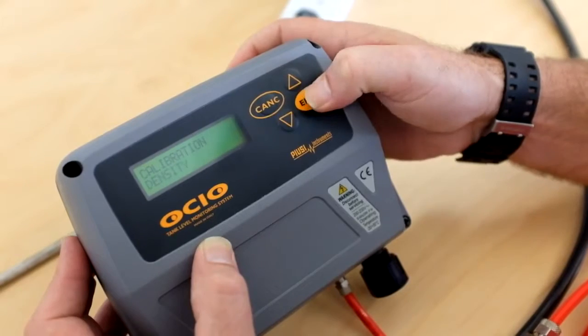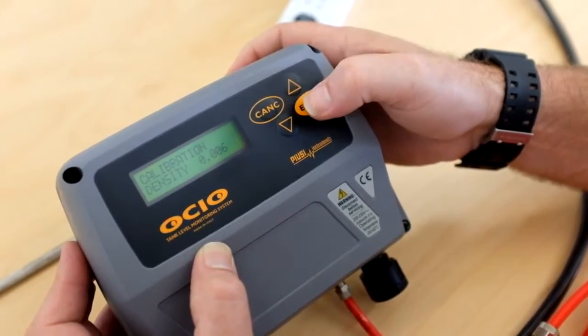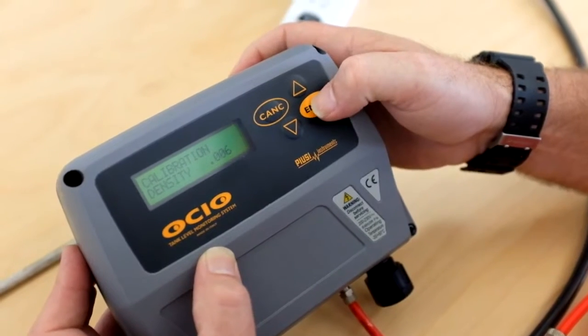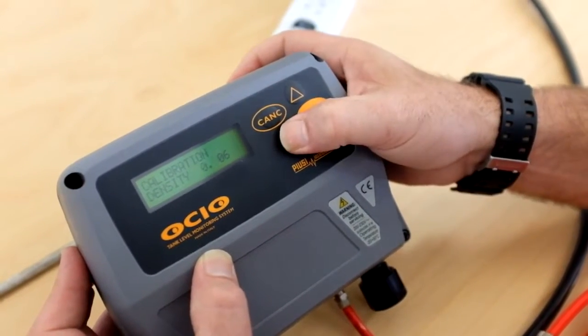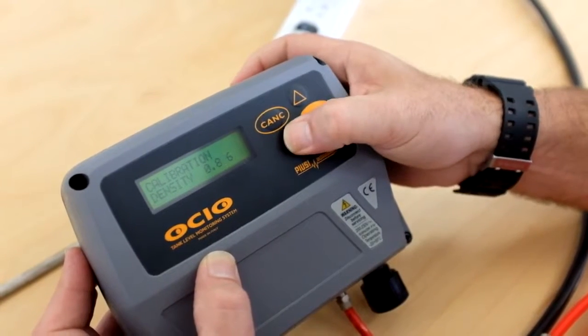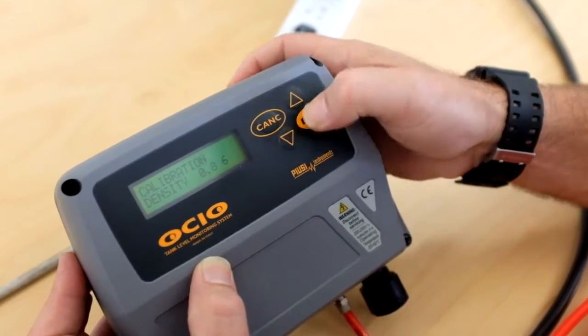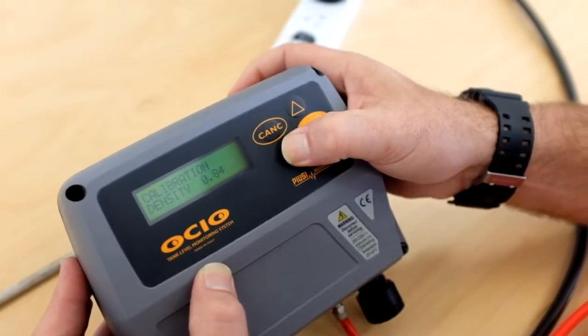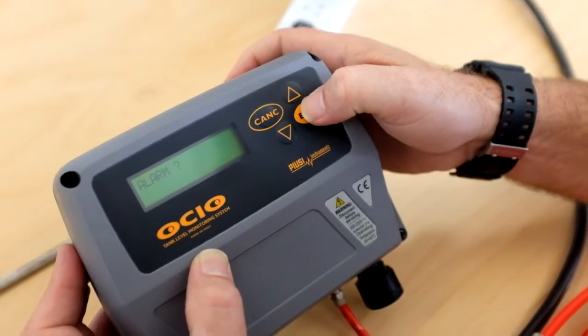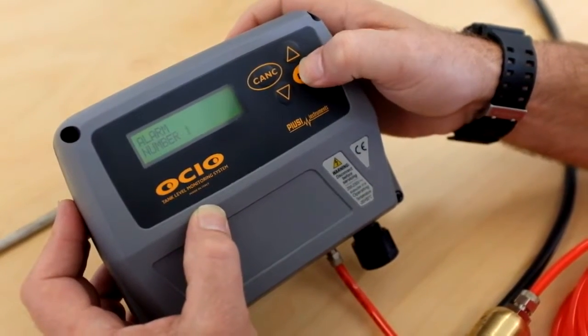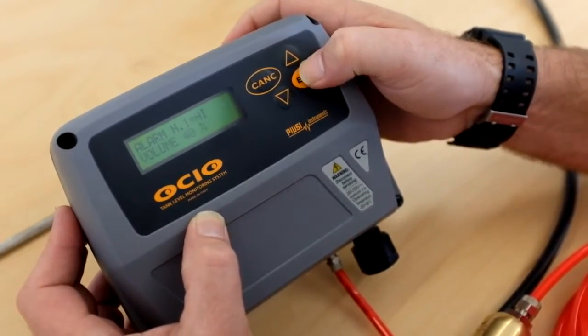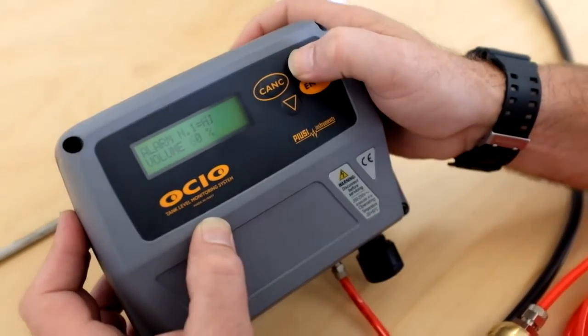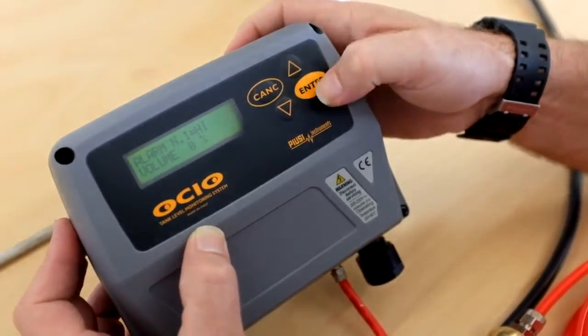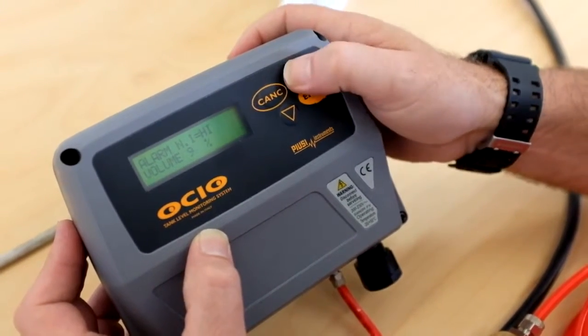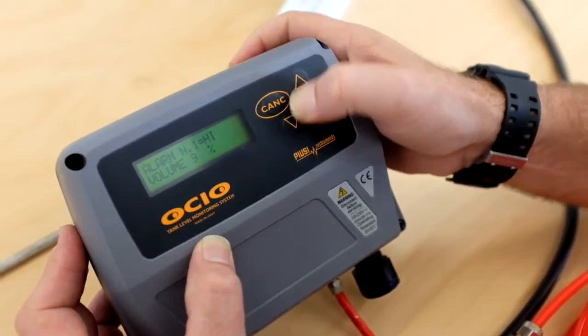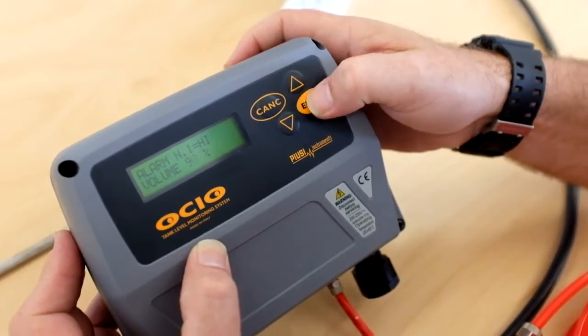Calibration, this is asking us what the density of the product is. So we have our density of diesel is 0.84. So we're just going to change this to 8. So we're setting this up for diesel. Out of the box, this will be set up for diesel. Alarms, so it's offering us alarm choices. Number 1 alarm is our high alarm. So we can change it to, at 80%, this will go into alarm state, or we'll change it to 95. Actually, we'll just leave it at 90.